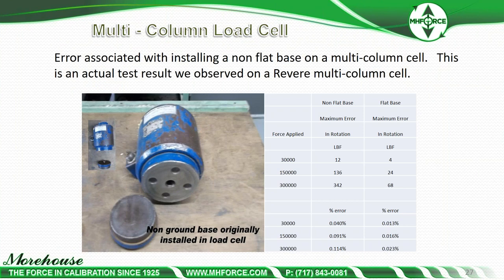Multi-column load cell example: we had this load cell with a non-ground, non-flat base. Before doing anything with it, we tested it. Maximum error with the non-flat base: 12 pounds when rotated at 30,000 pounds, 136 pounds at 150,000 pounds, and 342 pounds at 300,000 pounds. Then we ground the base flat and stoned it, then repeated the same test rotating 120 degrees. Our errors went from 0.114% down to 0.023%. Flatness is absolutely critical to ensuring repeatability of the load cell when rotated.